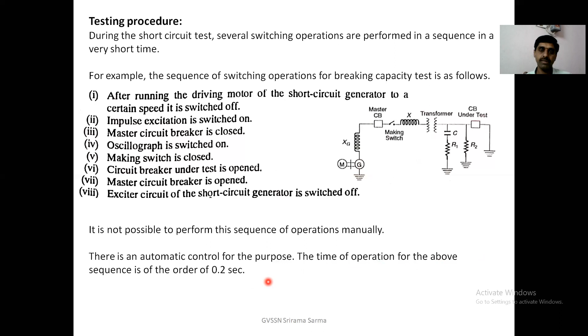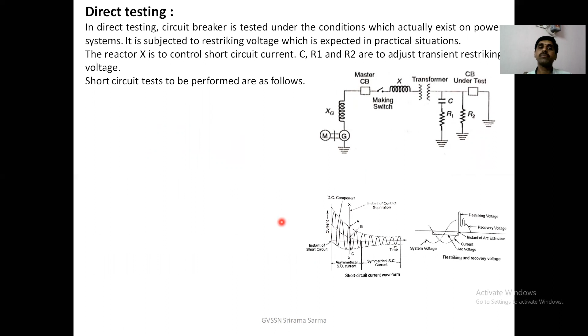So after this testing, again the master circuit breaker will be opened. The excitation, that means the exciter circuit of the short circuit generator, is switched off. So these are the steps involved in the sequence. It is not possible to perform this sequence of operations manually, so there is an automatic control for the purpose. The time of operation for the above sequence is of the order of 0.2 seconds. 0.2 seconds means just 200 milliseconds, which means 10 cycles. So we continue our discussion with direct and indirect testing in the next session.